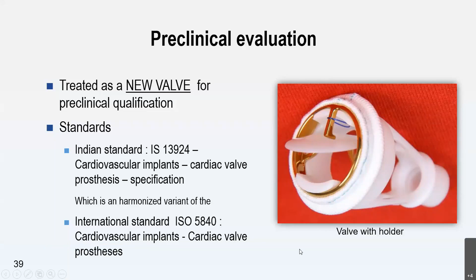And this is the valve with the holder in place. This holder will be removed after the valve is stitched onto the muscles of the heart. This is for aiding the surgeon in handling the device. It is normally suggested that the surgeon or others don't touch the surface of the device with their gloved hands, mainly because their gloves may contain some blood stains, which get transferred to the device and may create thrombus formation on that side. So a holder is provided along with the device to make sure that the surgeon doesn't touch the device during the stitching process.